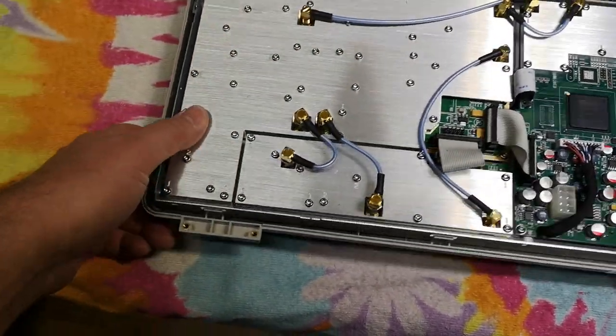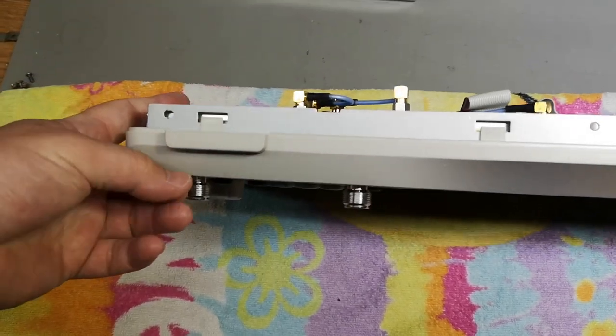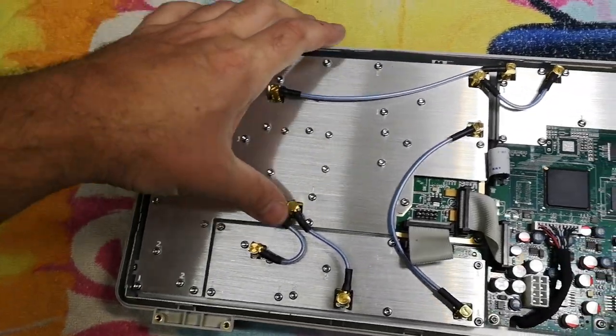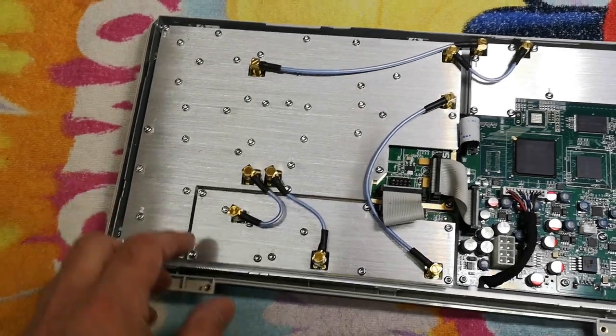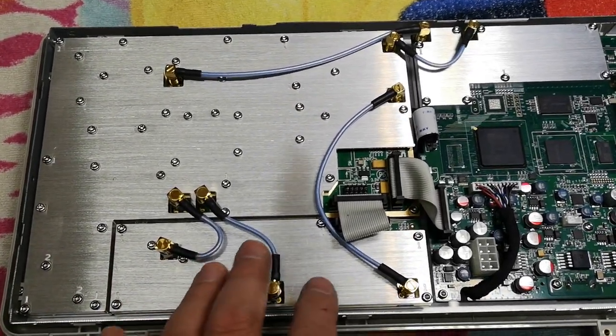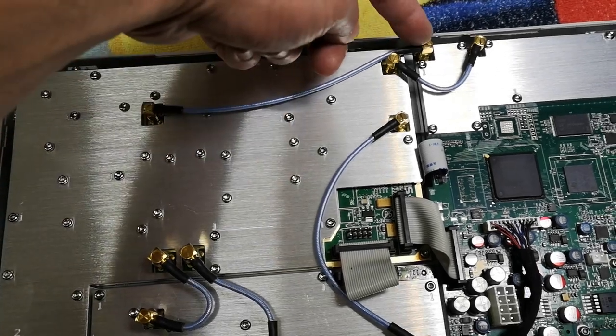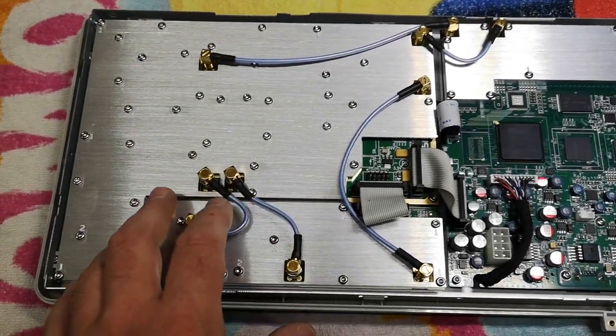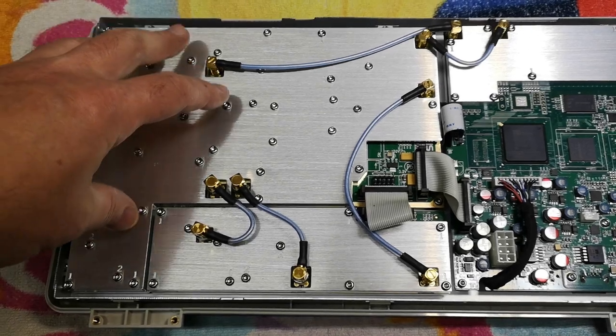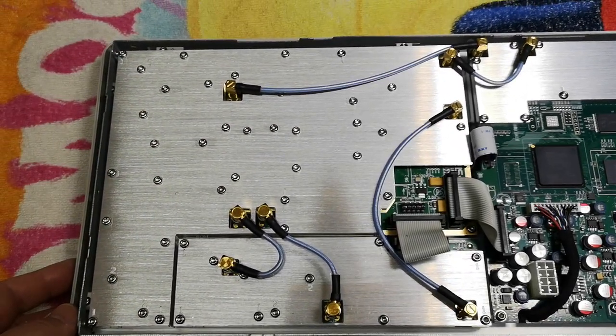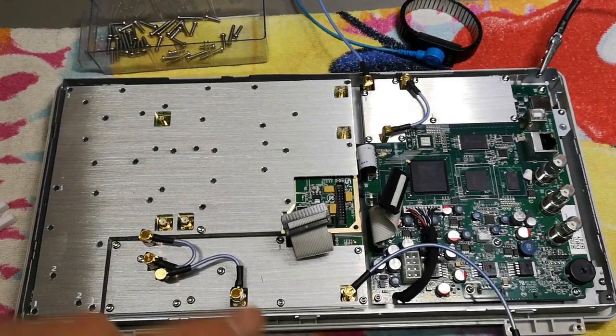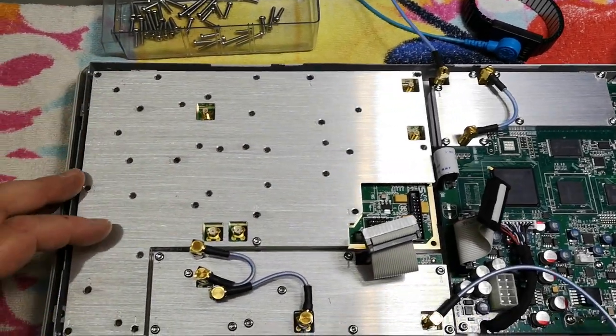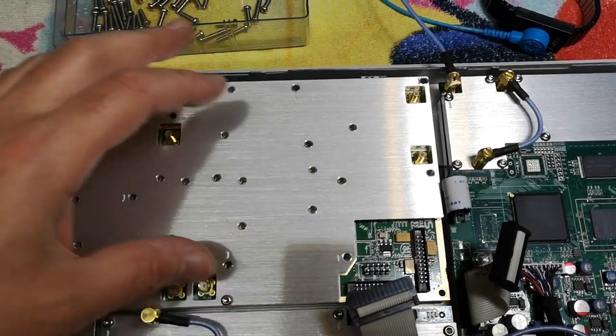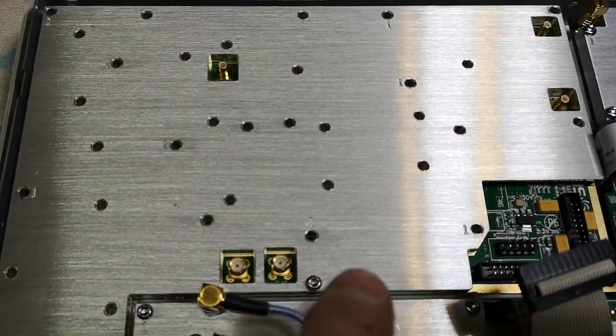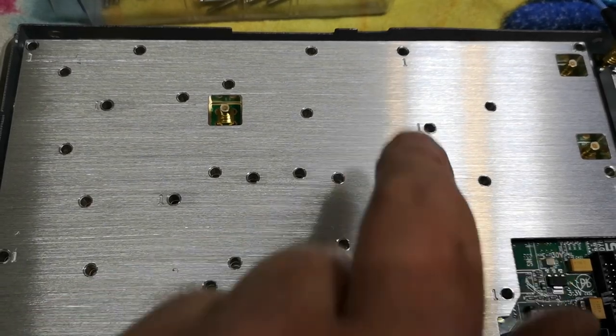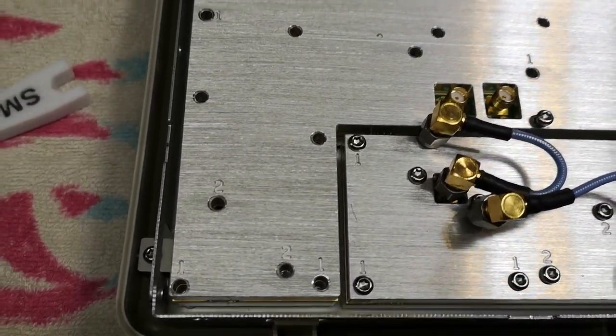Now we need to get this module. See, this is the input module. And this is the only thing we need to remove. So it's important to take all those pictures so you know exactly where everything is connected, because we need to take this board completely out to do service on it. They use different lengths of screws, so just be careful about this when you assemble it. They're really nice and friendly to mark the different lengths, so that is pretty cool.